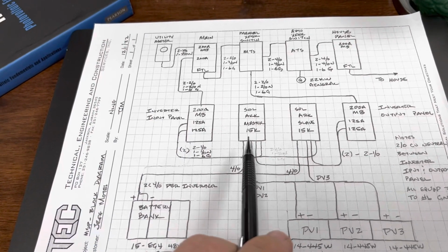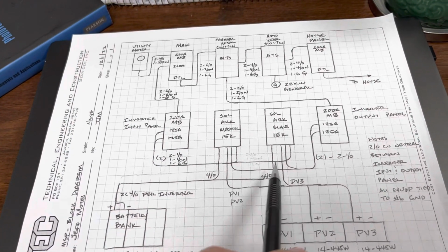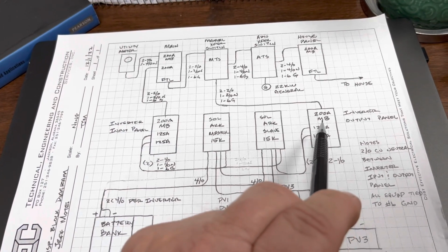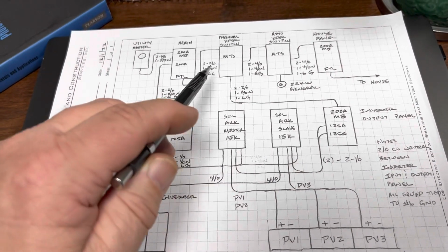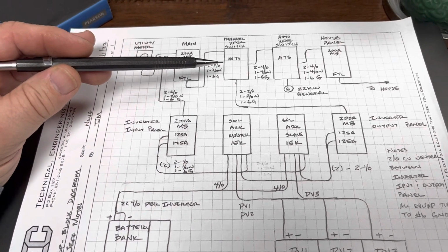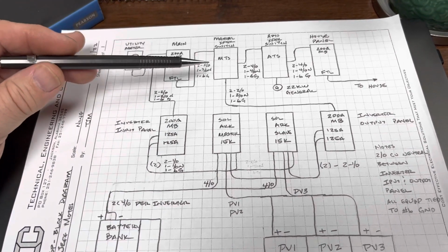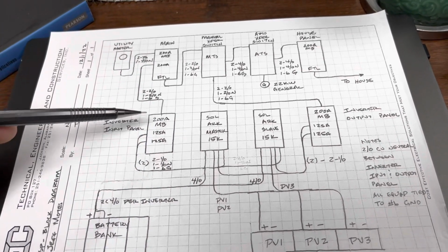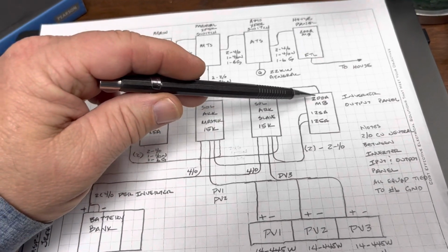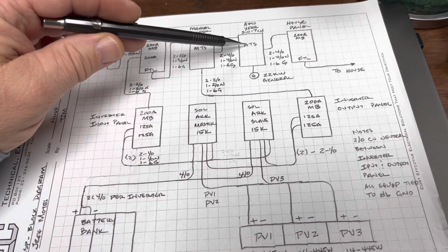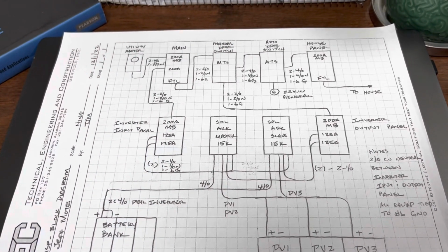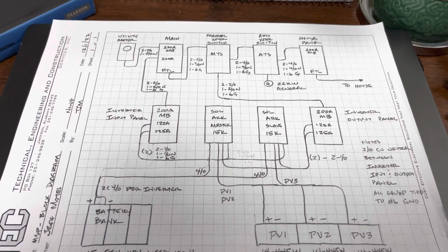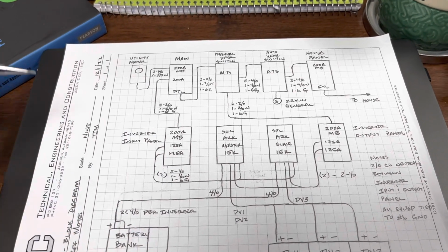On the load side of these inverters, I backfeed into another set of 125 amp breakers, and then backfeed out of a 200 amp breaker to the alternate source for this manual transfer switch. And when this manual transfer switch is in the alternate source, which I call my solar source, then power comes from the inverters through this panel to this switch, then back to the automatic transfer switch and on to my house. So that's how I'm interwiring my Sol-Arks.